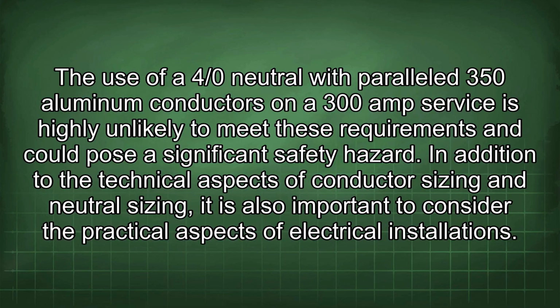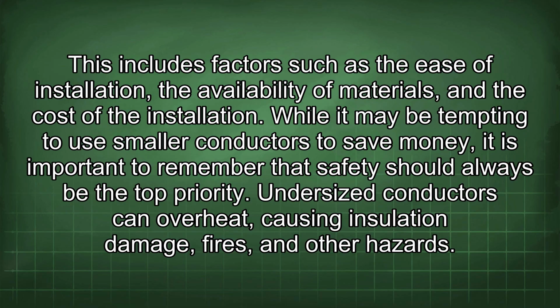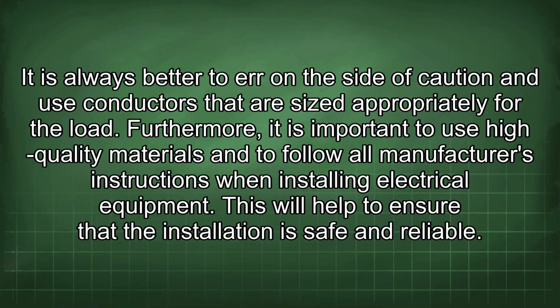In addition to the technical aspects of conductor sizing and neutral sizing, it is also important to consider the practical aspects of electrical installations. This includes factors such as the ease of installation, the availability of materials, and the cost of the installation. While it may be tempting to use smaller conductors to save money, it is important to remember that safety should always be the top priority. Undersized conductors can overheat, causing insulation damage, fires, and other hazards. It is always better to err on the side of caution and use conductors that are sized appropriately for the load. Furthermore, it is important to use high-quality materials and to follow all manufacturers' instructions when installing electrical equipment. This will help to ensure that the installation is safe and reliable.